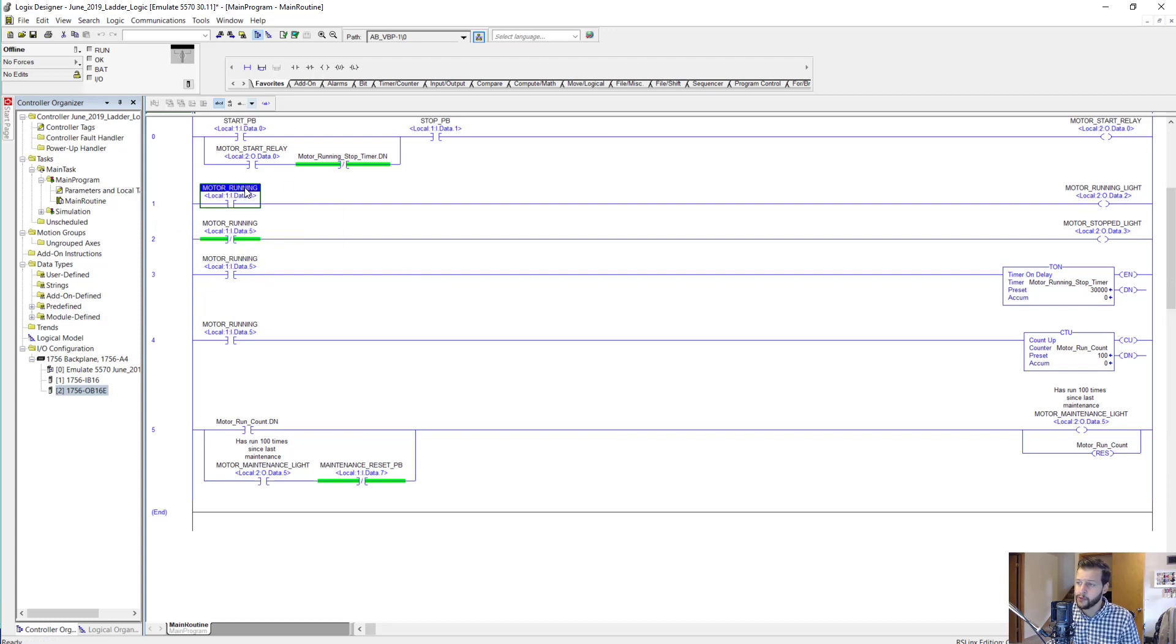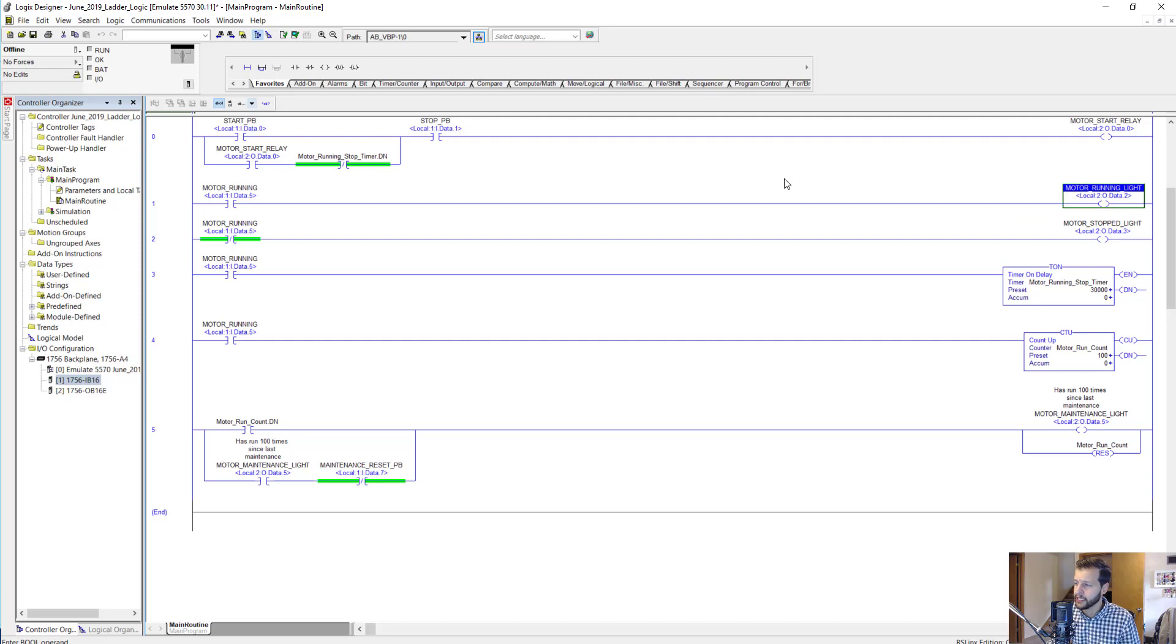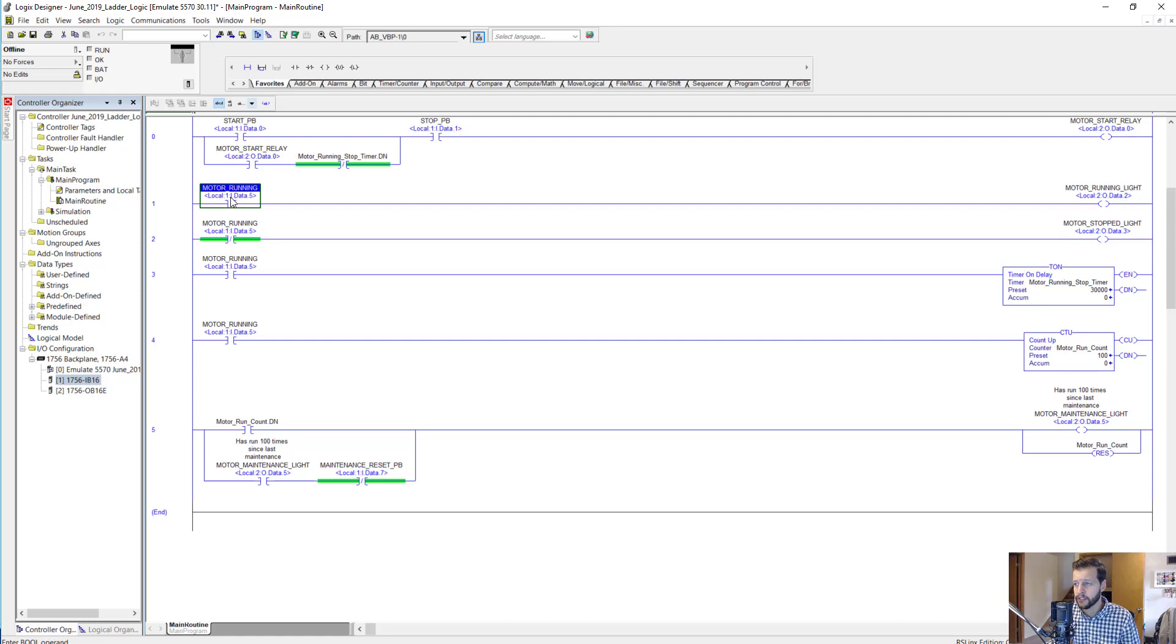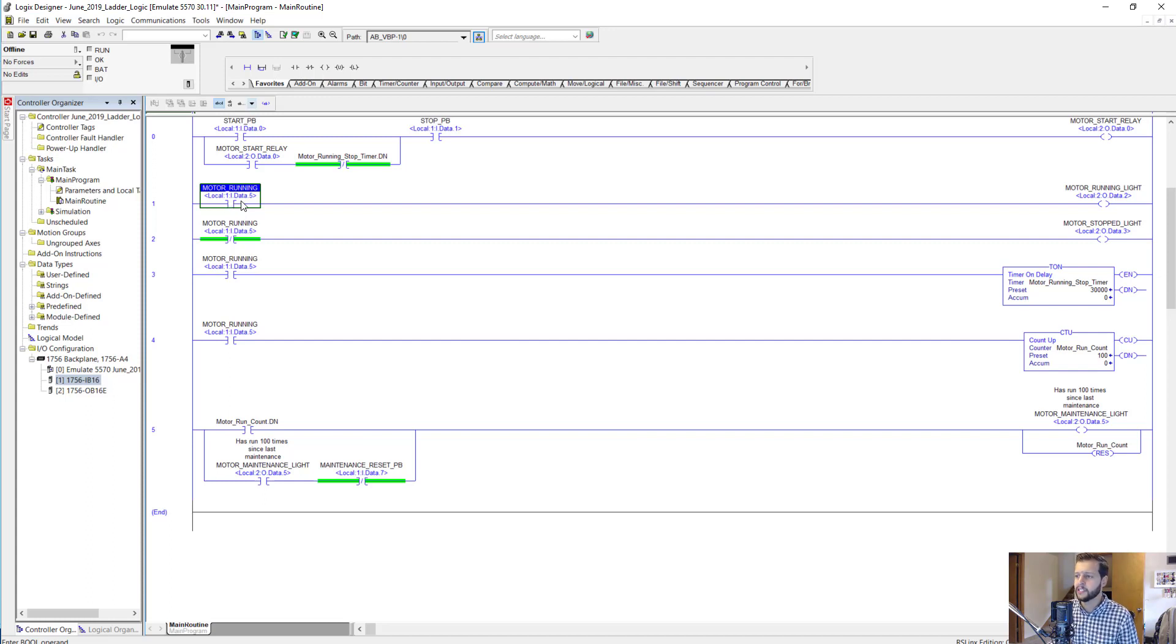Basically we use this motor running input which comes from slot 1 input 5, and we are either turning on the motor running light or we're turning on the motor stopped light. This motor running input would be something that is triggered once it sees the motor running at a certain speed. It could be some relay that detects that the motor has reached a thousand RPMs or whatever the speed needs to be, or it could be coming from a VFD or something like that.